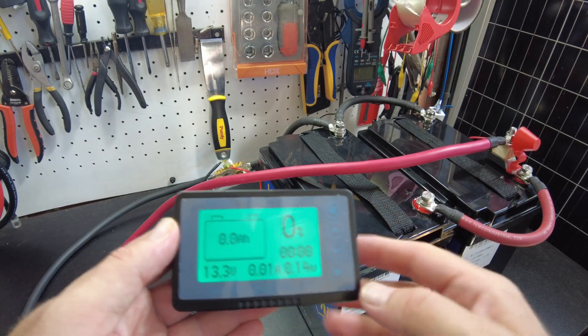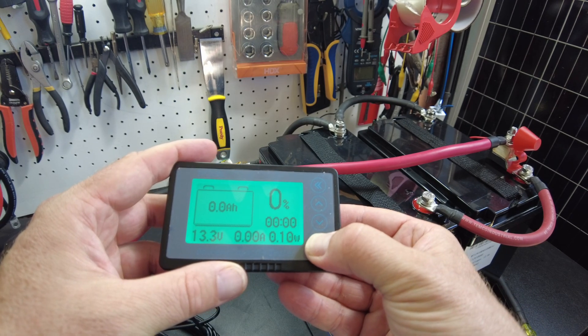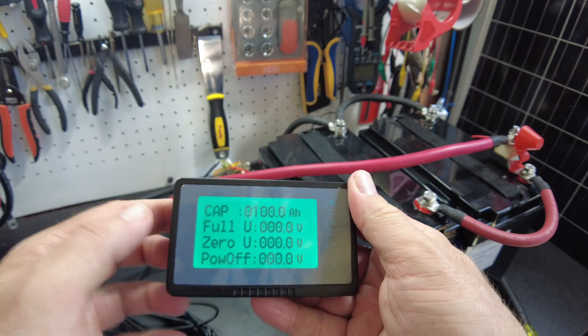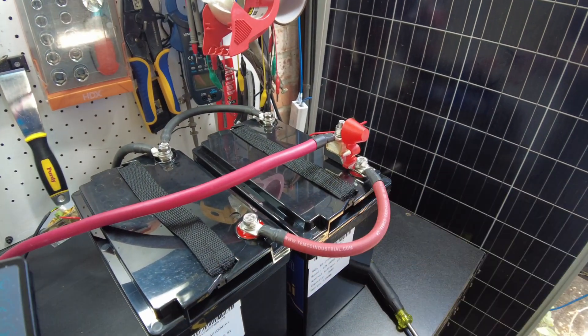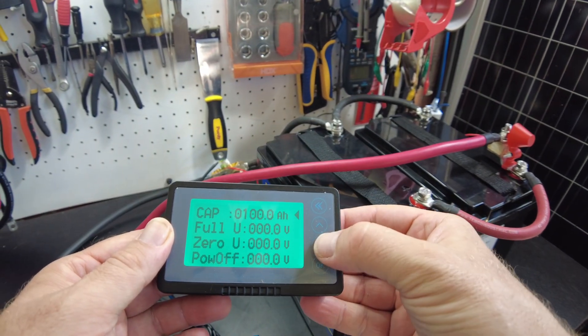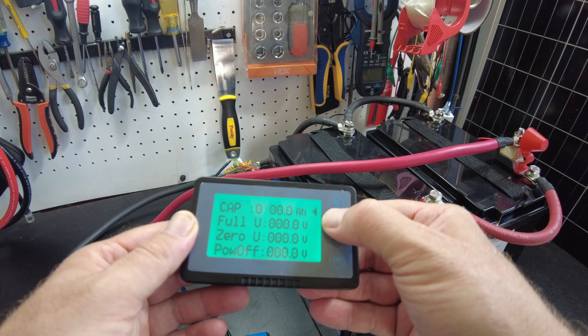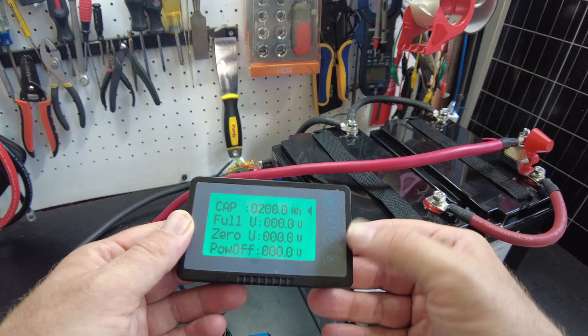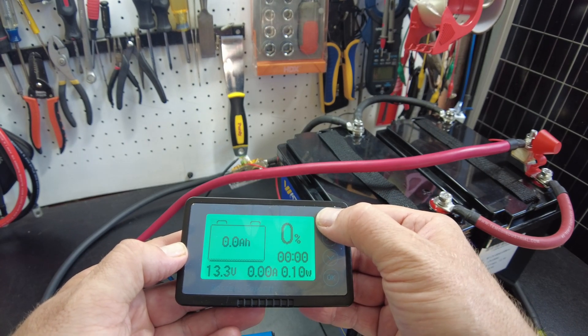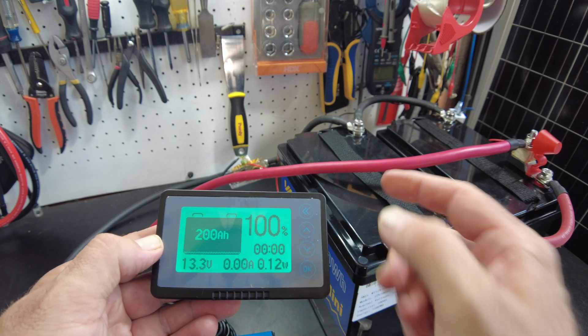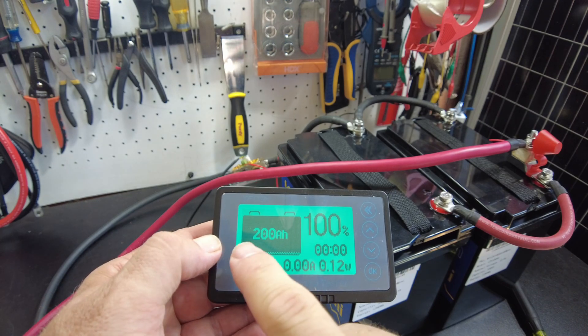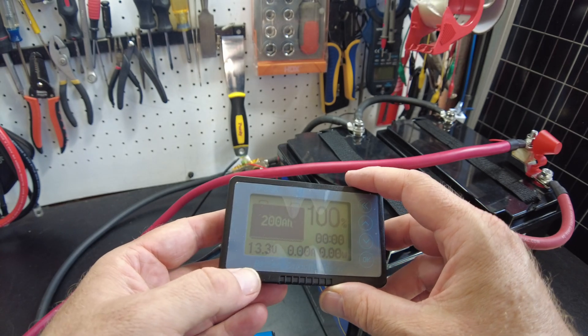Now, the batteries are fully charged. However, it is showing 0% on here because this is not set up. Let's go into the settings. So it's set to 100 amp hours. Since we have two 100 amp hour batteries in parallel, we need to actually set this to 200 amp hours. I think this is all we need to do right now. And I think in the manual it says you hold this up arrow down and then it resets it to 100%. There it is. So we are at 200 amp hours and 100%. Awesome.